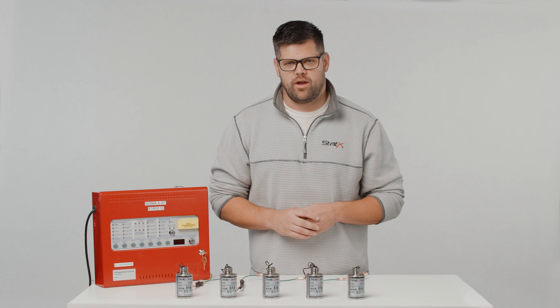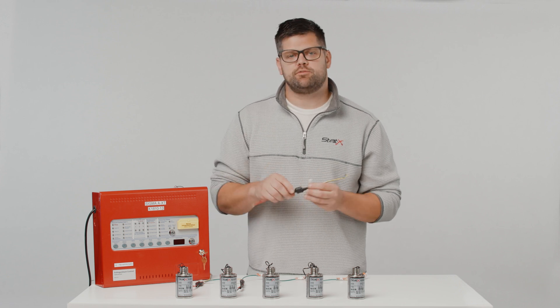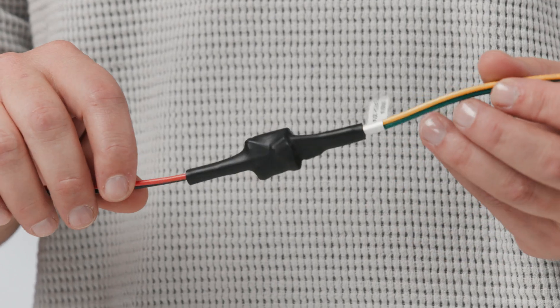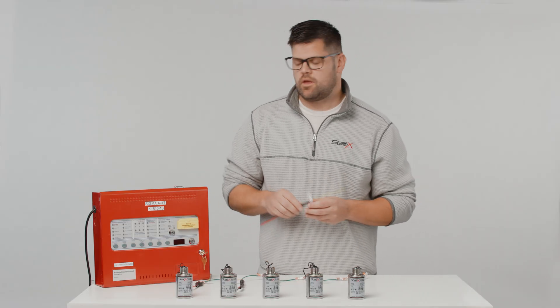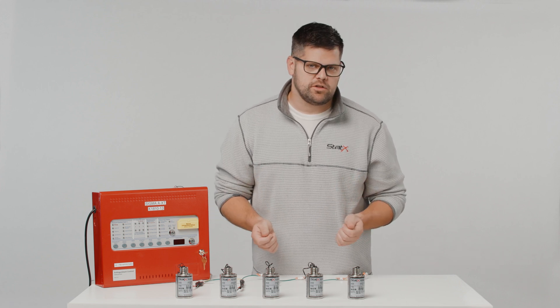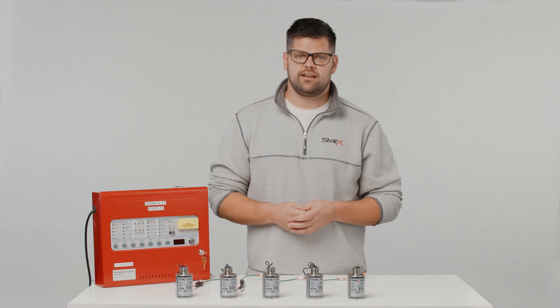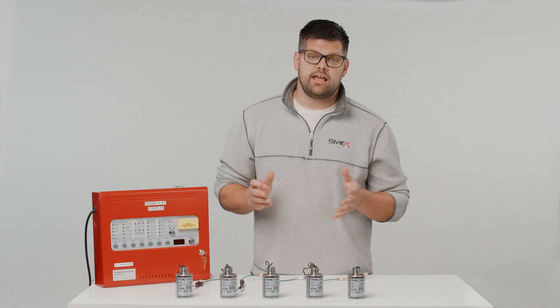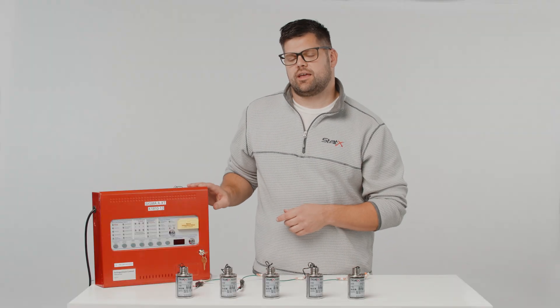Hey there, Jason here from FireWight. In this video I'm going to demonstrate how to connect an e-match protective device or EPD between a control panel and a Stat-X generator. We're installing an EPD to protect the system against high voltages like a lightning strike. This is also a requirement to comply with Stat-X UL listing. Today I'll show you how the EPD should be wired when connecting the generator with the Kentech panel.